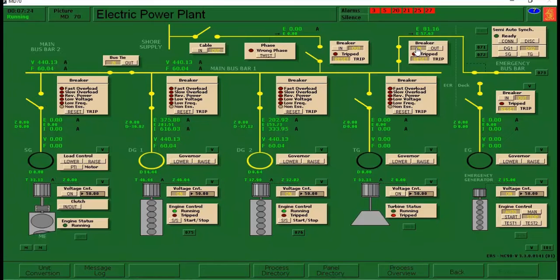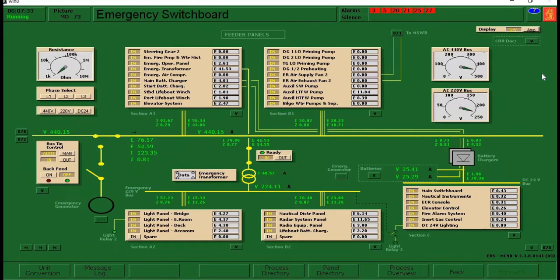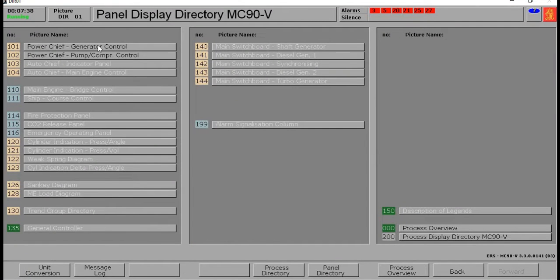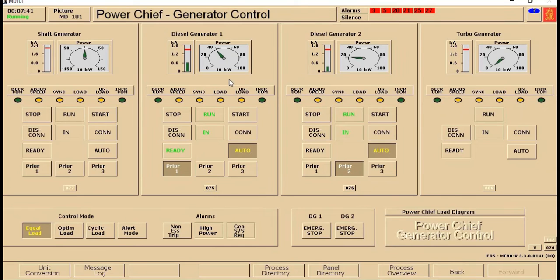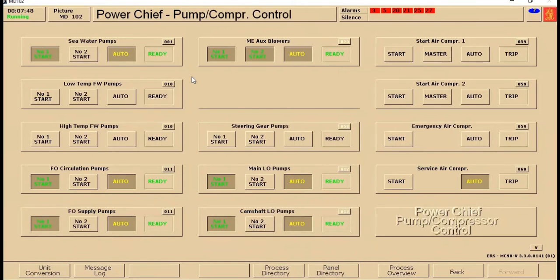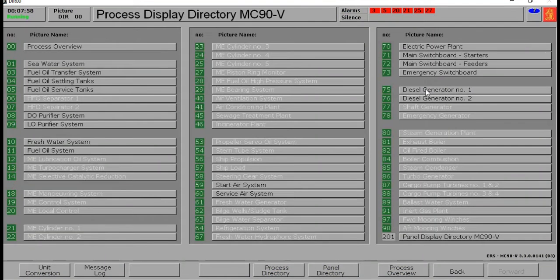Okay, let's go to electric power plant. Both our diesel generator 1 and diesel generator 2 are connected to the main bus bar right here. Okay. To our generator control, both of the diesel generator 1 and 2 are in auto. To pump control, so all our running pumps here are set into auto. So our system is running good.